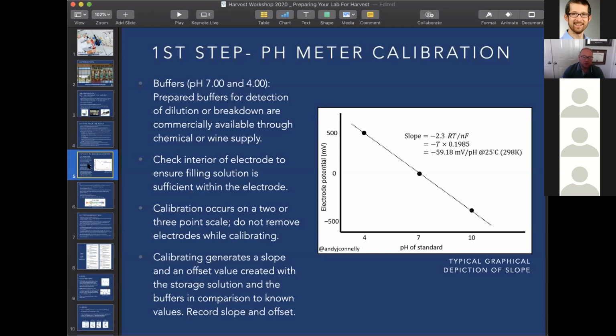So when you do calibrate, you want to definitely do that 2-point calibration. The 3-point is maybe a little bit better, though it can cause you some stress if those buffers are a little out of whack. What the calibration does is it generates a slope and an offset value.